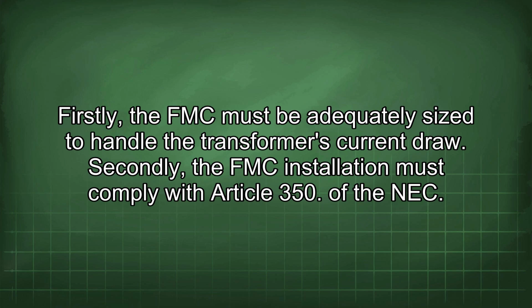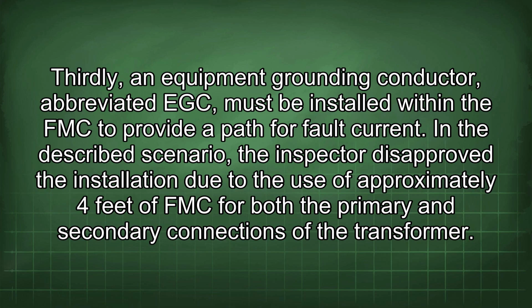Firstly, the FMC must be adequately sized to handle the transformer's current draw. Secondly, the FMC installation must comply with Article 350 of the NEC. Thirdly, an equipment grounding conductor, abbreviated EGC, must be installed within the FMC to provide a path for fault current.